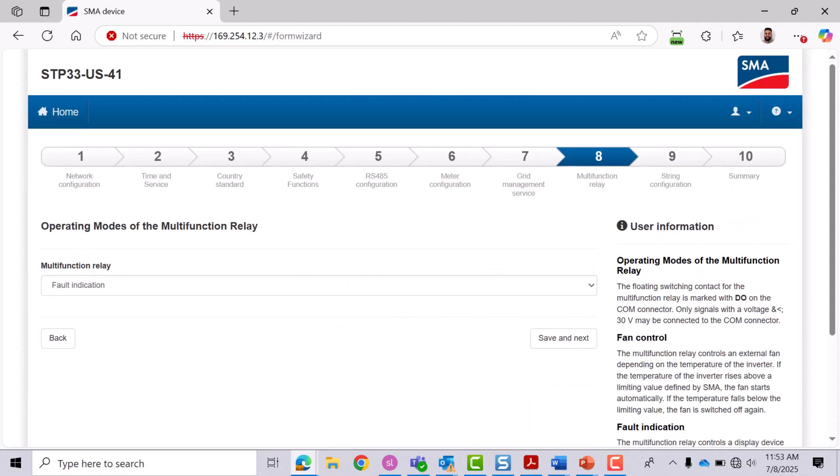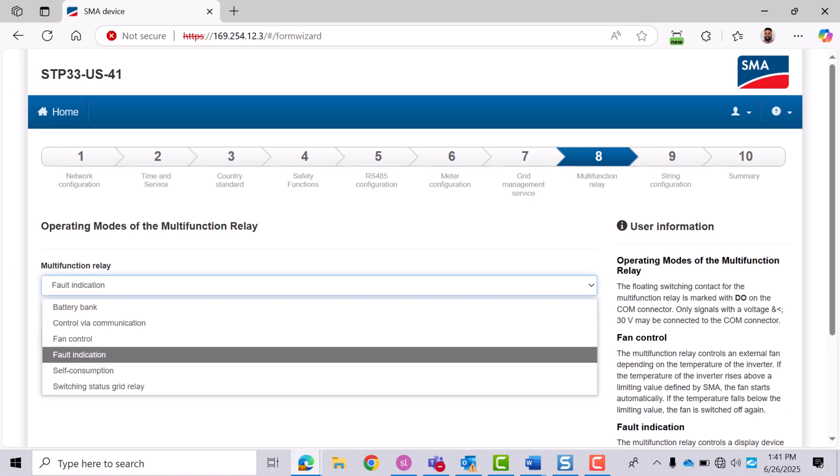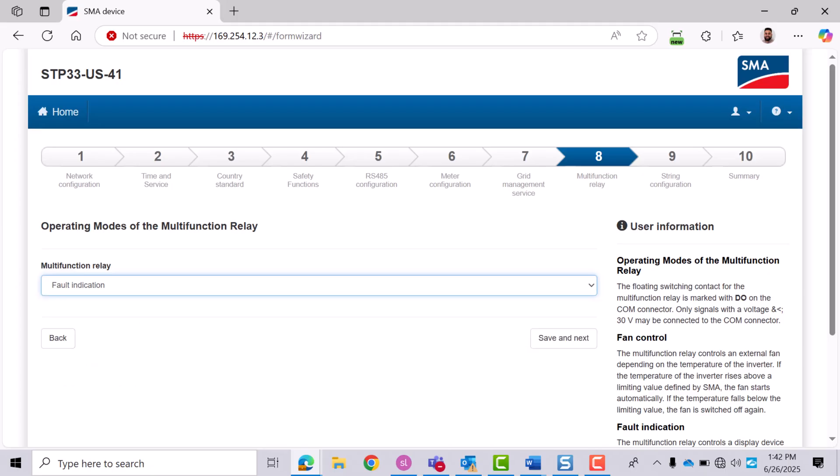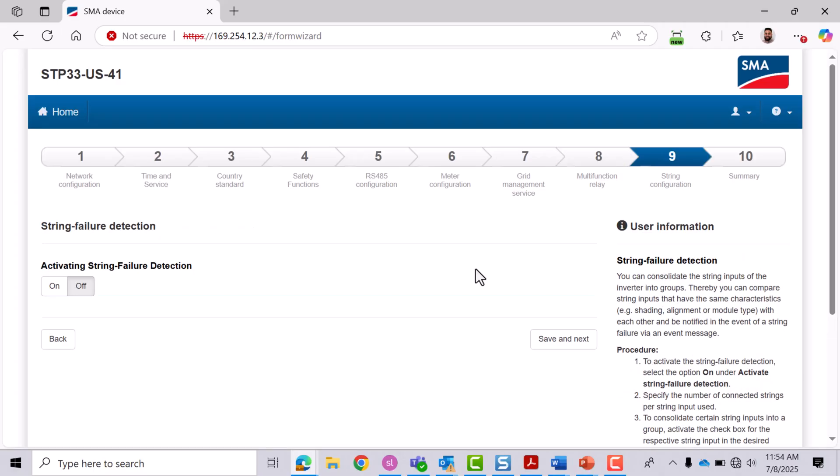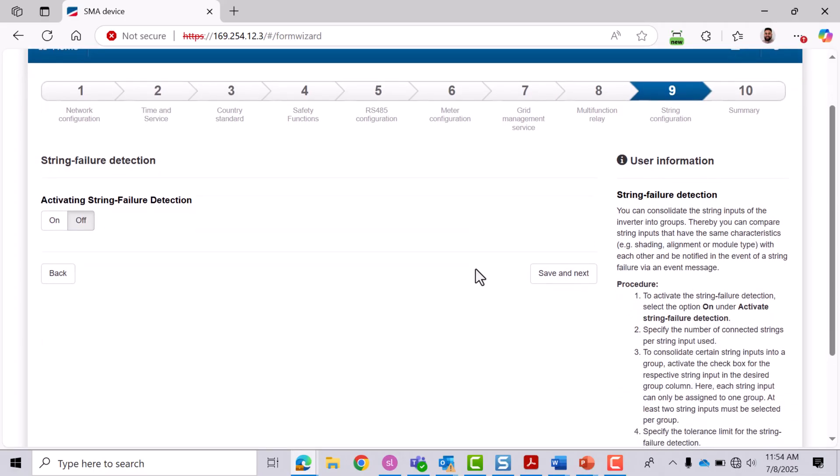In this menu, you can configure the multifunction relay. Unless equipment is wired to the multifunction relay port on the comms board, no action will occur. If nothing is connected, leave this set to fault indication and move on. Set up string failure detection.